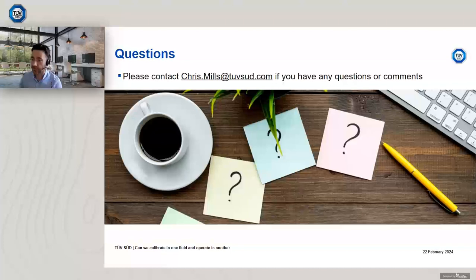Someone's asked, are the results shared for a particular Coriolis meter manufacturer or design, or is it common for all Coriolis meters? Now, it's a good question. We are fortunate that we see the vast majority of Coriolis meter manufacturers here at TÜV SÜD. I won't name them, but everyone's aware of the main manufacturers, and they have slightly different designs. So you have ones with what's known as the U-tube, a pronounced bend in the design, and we have ones with, say, a curved tube. We have ones that are straight tube, and these devices often operate, or they certainly do operate, at different oscillation frequencies.